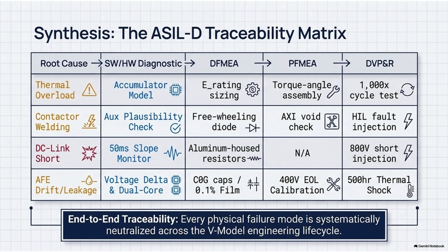And crucially, after the 500 hours are over, they don't just plug it in and say, well, the light turned on, we're good. They perform a destructive physical analysis, or DPA. What's that? They take precision diamond saws and physically slice the components open. They place the cross-sections under electron microscopes to prove definitively that the solder layers have zero propagating microcracks, and that the high-voltage isolation resistance separating the 800-volt pathways from the low-voltage logic remains robustly above 100 megohms. They prove the unit isn't just surviving the abuse, it is shrugging it off.